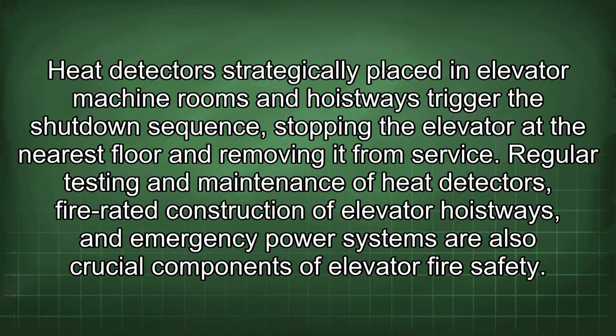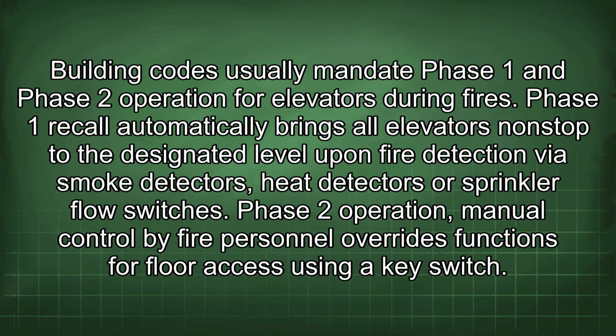Regular testing and maintenance of heat detectors, fire-rated construction of elevator hoistways, and emergency power systems are also crucial components of elevator fire safety. Building codes usually mandate Phase 1 and Phase 2 operation for elevators during fires. Phase 1 recall automatically brings all elevators non-stop to the designated level upon fire detection via smoke detectors, heat detectors, or sprinkler flow switches. Phase 2 operation, manual control by fire personnel, overrides functions for floor access using a key switch.